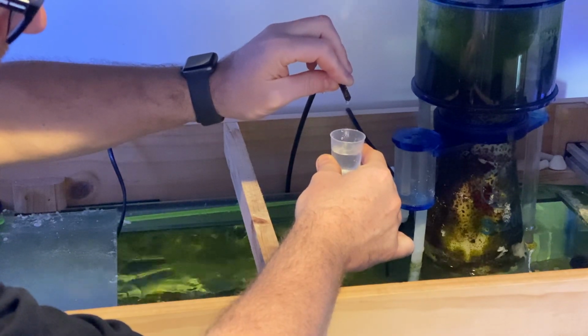Now, I could comfortably say that that means it's holding calibration and everything's hunky-dory, but that wouldn't be fair because I did not measure it at the start. I'll give it another month or two and I'll measure it again to see if we're still at 50 mil a minute. Bear in mind, if it does drop off a little bit, or even if it increases a little bit as the pump frees up or something, that's not actually a huge problem. Anything that's running 24/7 and you're expecting it to be at a milliliter per minute level of accuracy, you've got to expect a little bit of variance there, and you're gonna have to calibrate it every quarter or every 6 months at worst, if you're needing a precise instalment.